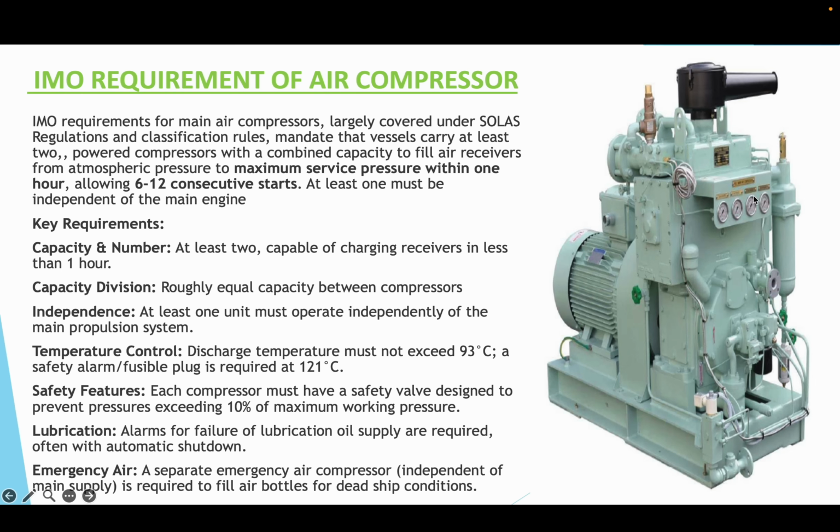So IMO says that the air compressor on board should be at least 2 in number, and those 2 compressors should be able to fill the air bottle such that it will be able to give the required number of starts as per the reversible and non-reversible engine.